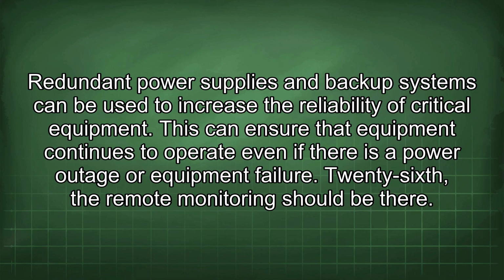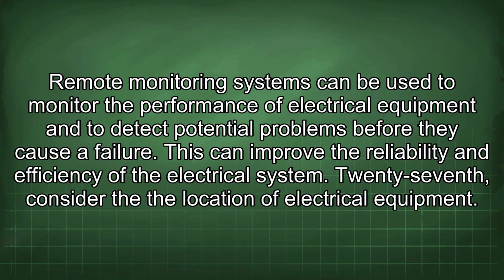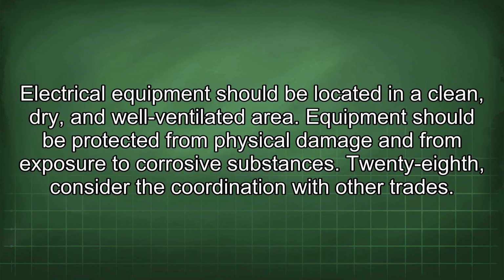26th, the remote monitoring should be there. Remote monitoring systems can be used to monitor the performance of electrical equipment and to detect potential problems before they cause a failure. This can improve the reliability and efficiency of the electrical system. 27th, consider the location of electrical equipment. Electrical equipment should be located in a clean, dry, and well-ventilated area. Equipment should be protected from physical damage and from exposure to corrosive substances.